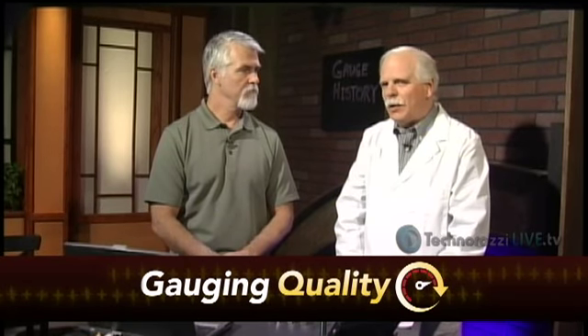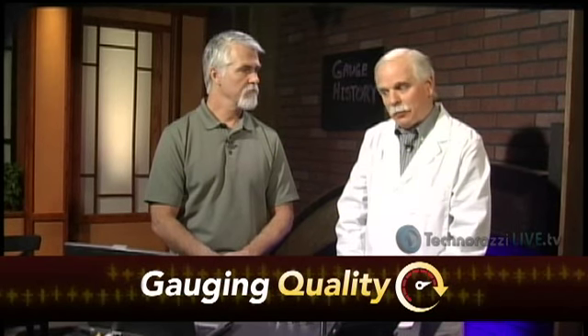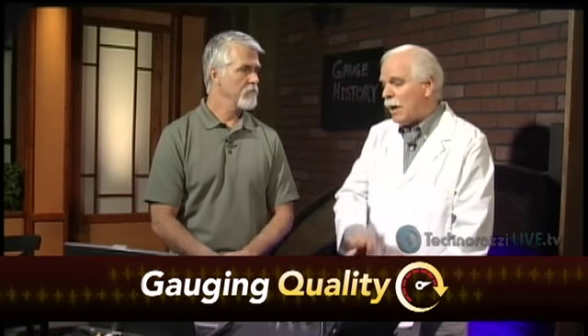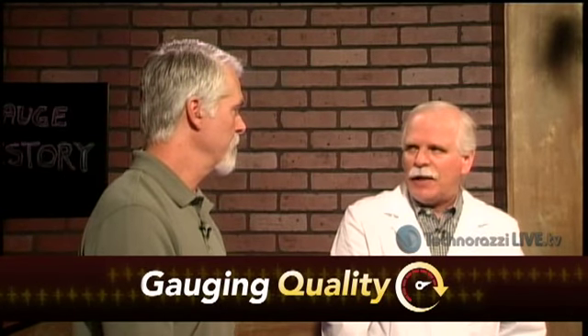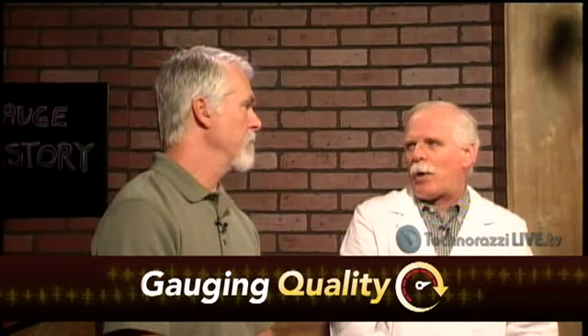You'd say, well, this gauge is just 10 millionths on the minus side. But if you had a history, you could look at it, again, with a click of a button. You could see how it's trending, and then all of a sudden, it just drops off. You'd know further investigation is needed. It might be used in a ceramic environment, which is abrading. Or maybe somebody dropped it. Or they dropped it and didn't mention that.